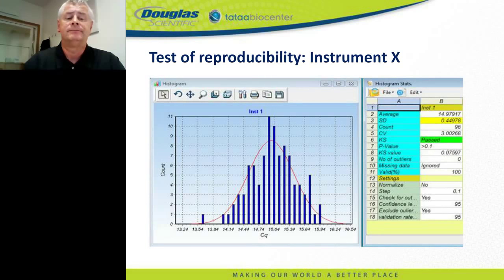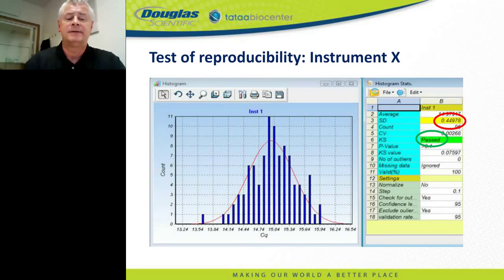The first test is for normality, which passes — the variation of CQ values across replicates is normally distributed, as expected. The standard deviation of the replicates is 0.087 cycles, far below the 0.25 cycles claimed by the majority of qPCR instrument providers. Not all instruments perform this well. In one example from our regular QC controls, a test passed normality but had an unacceptably high standard deviation of 0.45 cycles. We found a filter in that instrument was offset, likely bumped accidentally. Another instrument had a standard deviation within spec at 0.246 but showed a bimodal distribution — it had two Peltier elements not synchronized, resulting in a small temperature difference between sides of the block. In both cases, there was no error message from the instrument; the problem was only discovered through the QC scan.